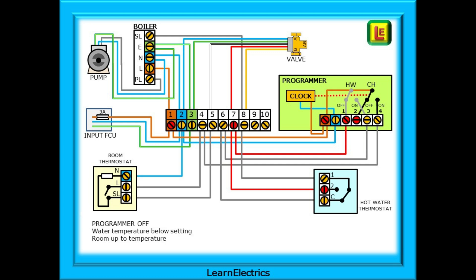What happens if the water thermostat changes over whilst the programmer says water off? We still have 240 volts on programmer terminal number one and this supplies 240 volts onto wiring center seven and from there along the grey wire, which means that the hot water is not enabled. Now the programmer changes state to hot water only. If the water is already up to temperature, what happens next? Programmer terminal three is at 240 volts and this puts 240 volts onto wiring center number six terminal. From six, the 240 volts goes down to the water thermostat at C, through C onto two, and back up to seven at the wiring center. This puts 240 volts on the grey wire to the valve and signifies hot water not required. From seven it also goes back to the programmer, but this is of no consequence, so nothing happens, no hot water heating.